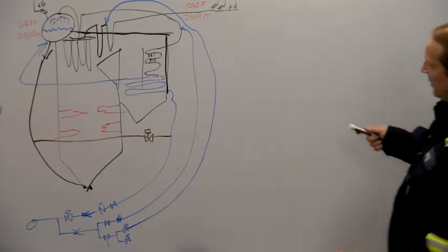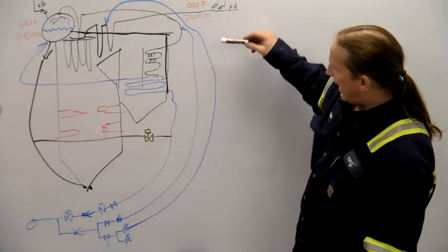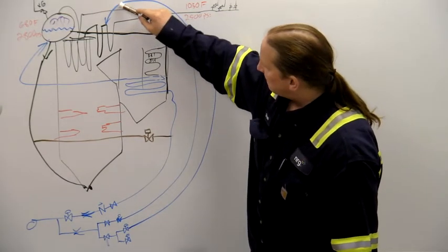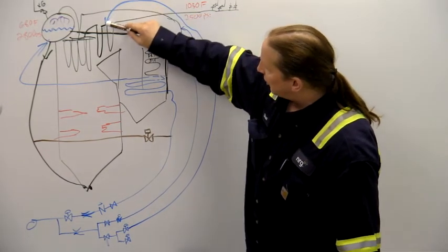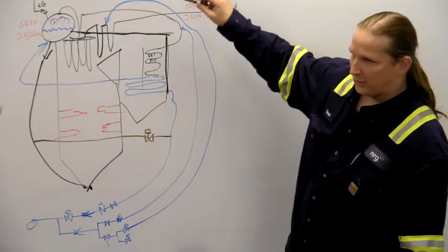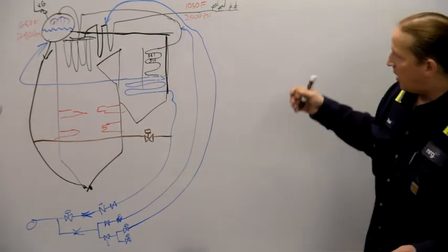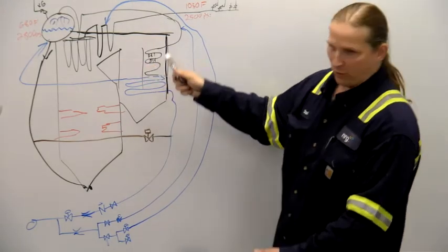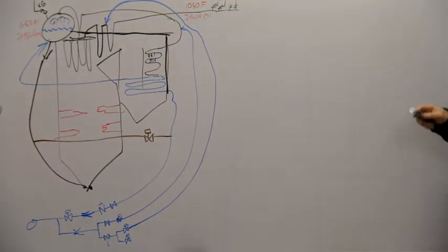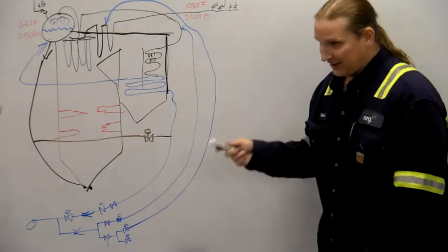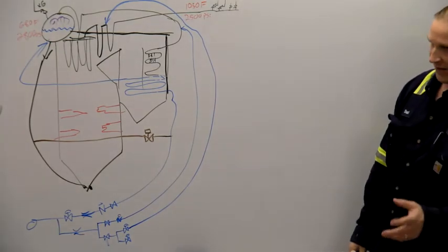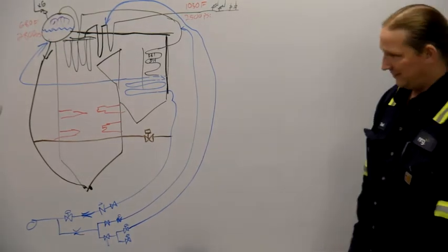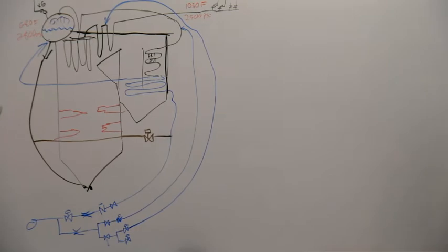It's a design thing. You clearly have to have a superheat section downstream of this that's going into the tertiary, to make sure that any water you spray in there gets fully boiled off before you get to the turbine. Because the turbine is meant to have gas in it, steam in it, it's not meant to have water in it. Water is way denser and it's bad for the blades.